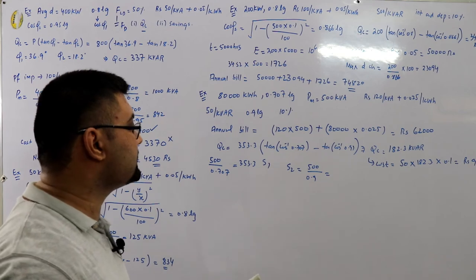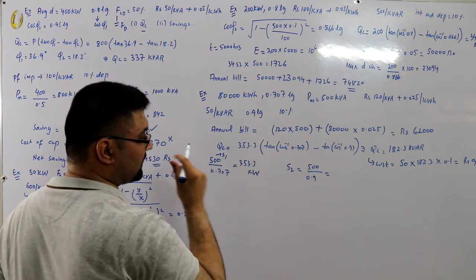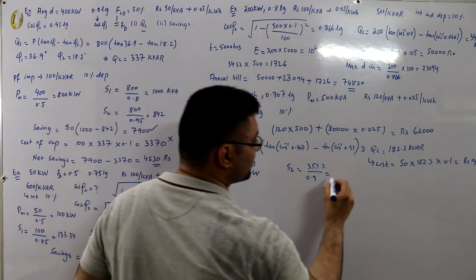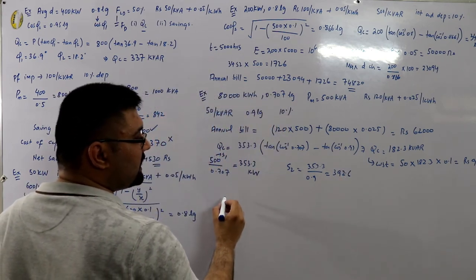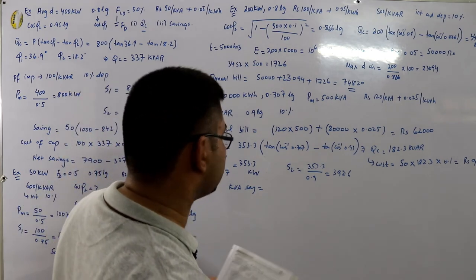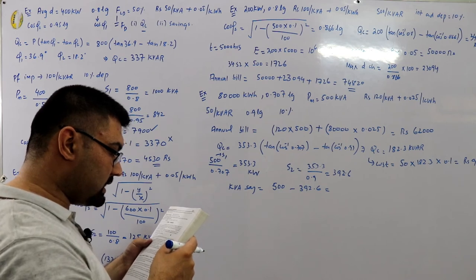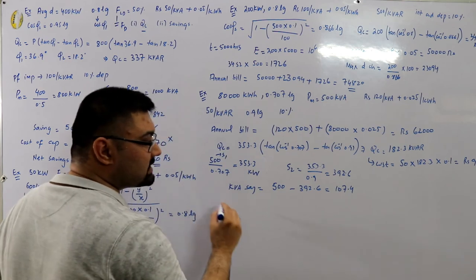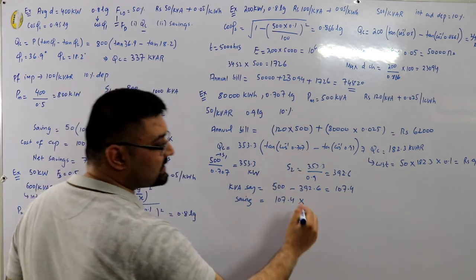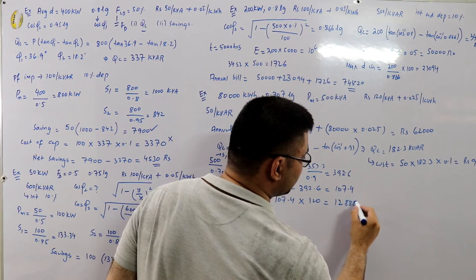kVA has reduced from the initial 500 to the new value of 392.6, a reduction of 107.4 kVA. Saving from kVA reduction = 107.4 × 120 rupees per kVA = 12,888 rupees annually.